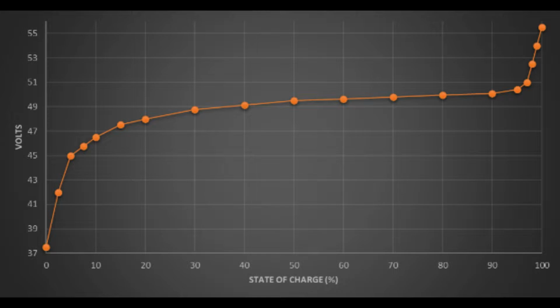So if the voltage gets too high, for example above, say, 55 volts, there could be permanent damage, or worse, these batteries could catch fire and explode. And conversely, if the battery pack gets too low, for example below 41 volts, the batteries could be permanently damaged and become unusable.